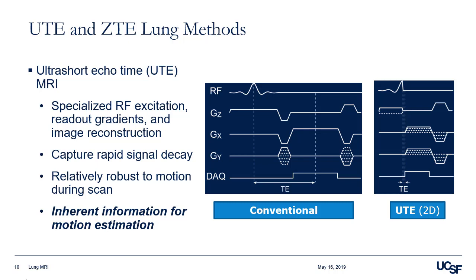Most proton-based imaging is done with ultra-short echo time or zero echo time — UTE or ZTE methods. For this talk I'll focus mostly on UTE methods, but a lot of these principles apply to ZTE as well. As a brief overview, we use specialized RF pulses, usually center-out type or close to center-out readout gradients, and associated reconstructions to capture the rapid signal decay. A joint benefit of these pulse sequences is that they're relatively robust and have some inherent motion information in them, which is very valuable.